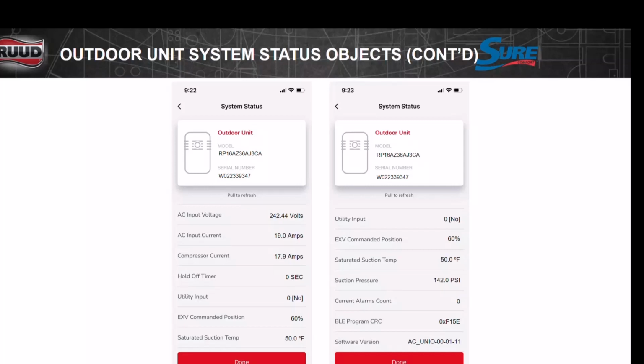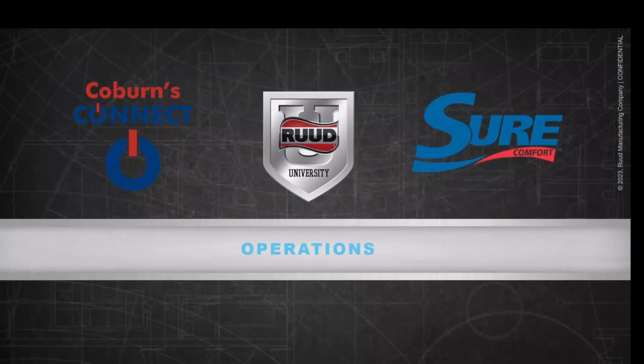Suction pressure, saturated temperature, all the stuff that we need to normally go to our gauges and get is right there on the control. How simple is that? Tells you everything you need to know. Pretty much, right? I mean, you can go there and open that up and tell, before you even put your gauges on it, what you've got to get out of the truck, basically.